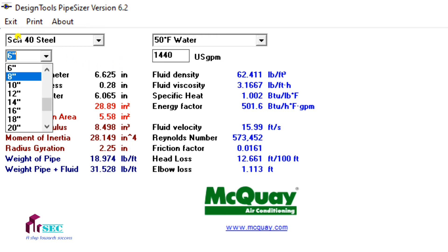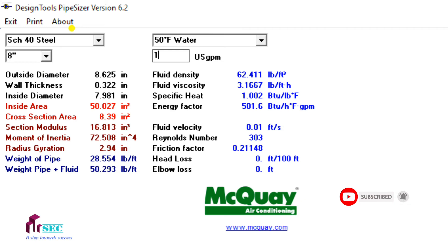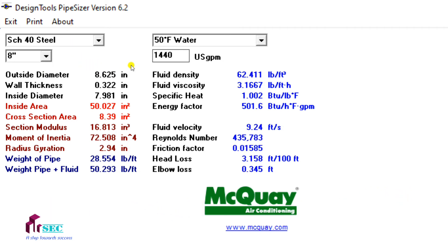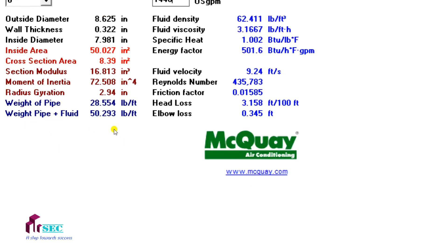So check with 8 inch — simply select this pipe size and enter the GPM. Now you can see the fluid velocity is 9.2 feet per second, which means this meets your condition.